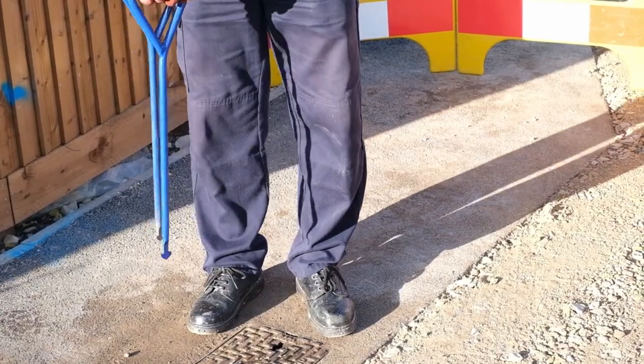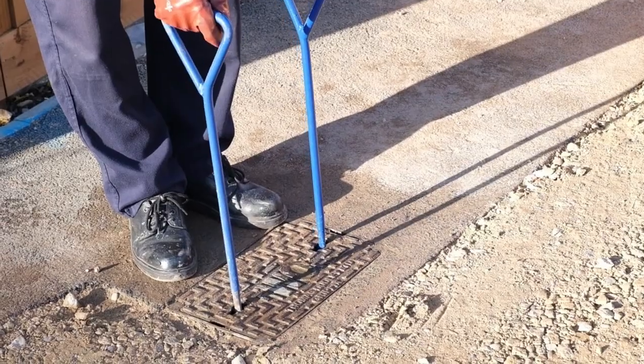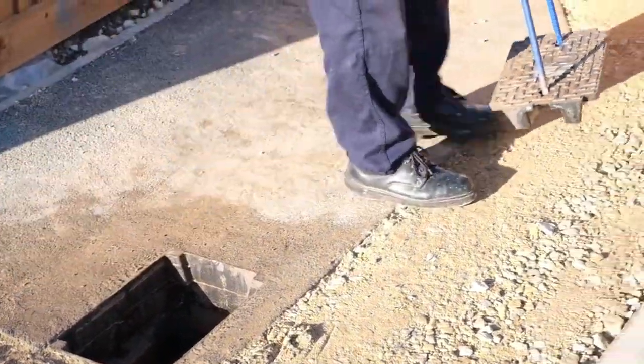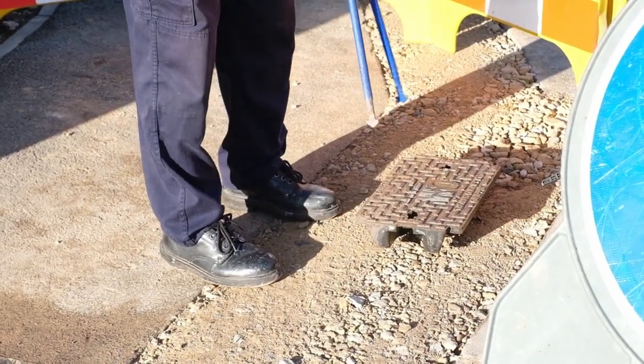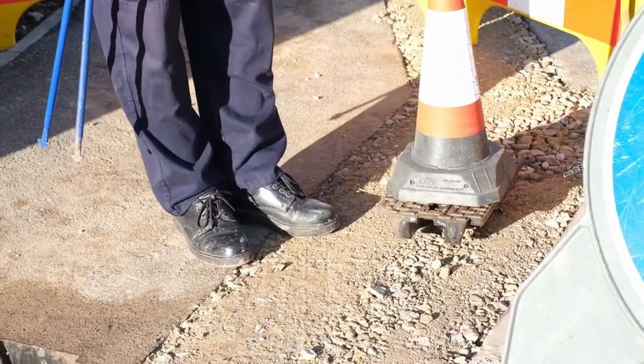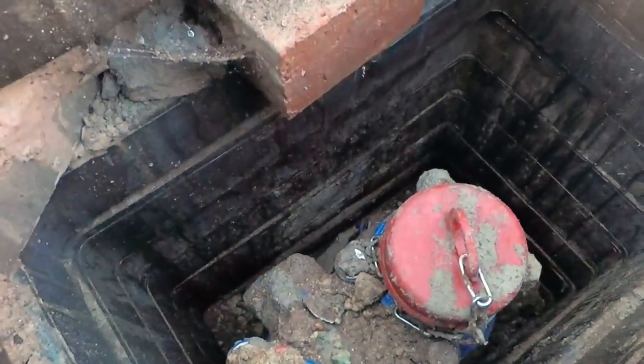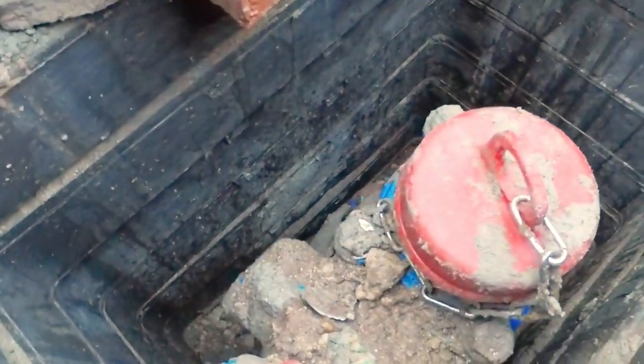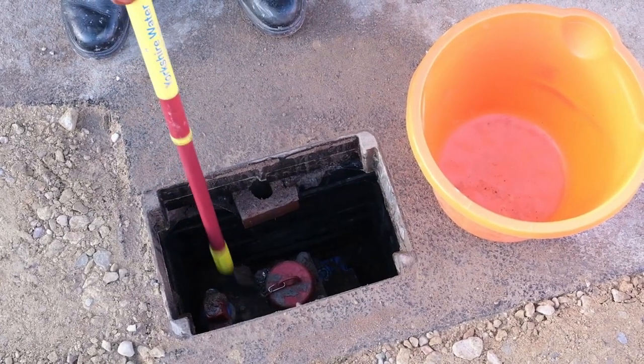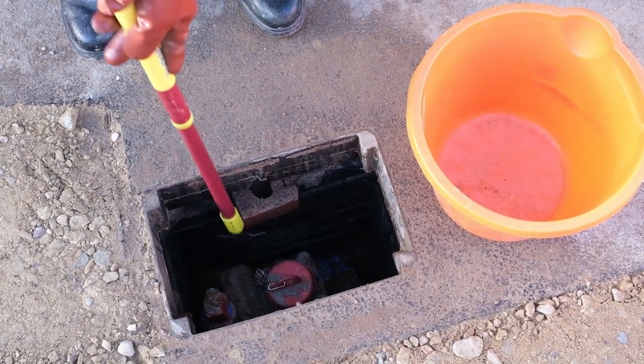Here's a step-by-step guide of how you should operate a hydrant. Firstly, open the washout hydrant using the lid lifting keys. Check that you have selected a usable hydrant. If a hydrant has been damaged by misuse or there's a leak, report it. You could potentially be stood on a sinkhole — safety first, replace the lid, report it and find another washout hydrant. Use the appropriate tools to clean out any debris in the hydrant pit. Remember, never put your hand directly into the pit.